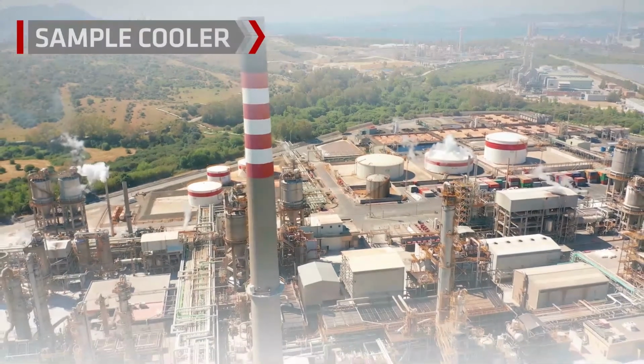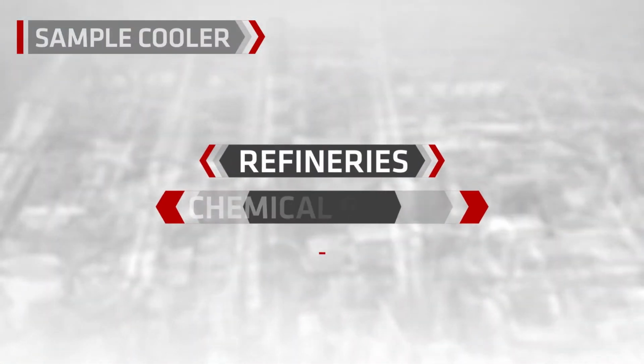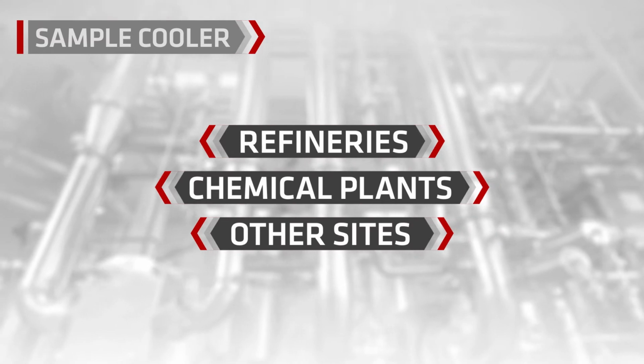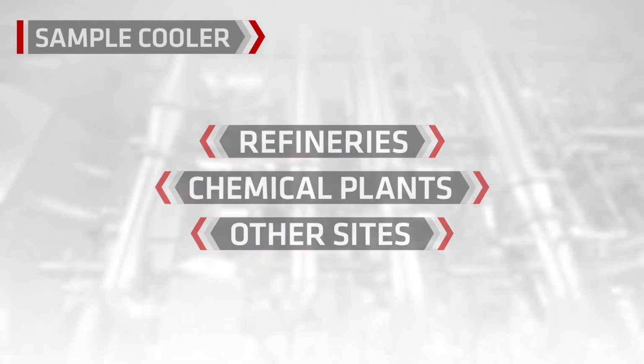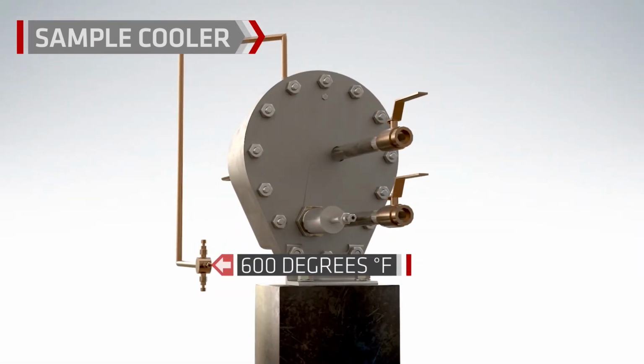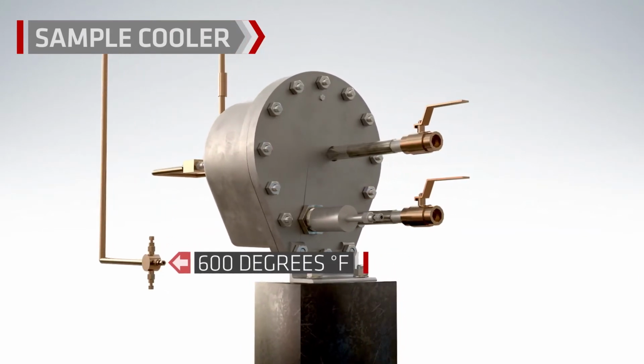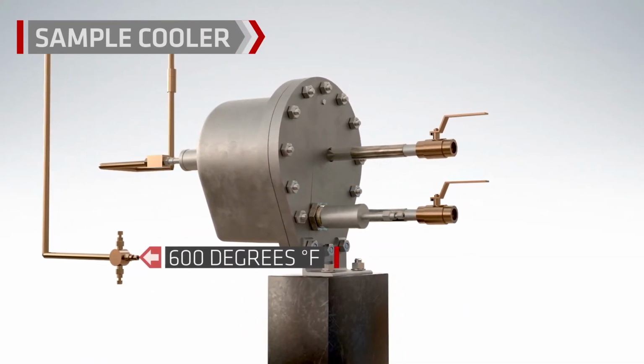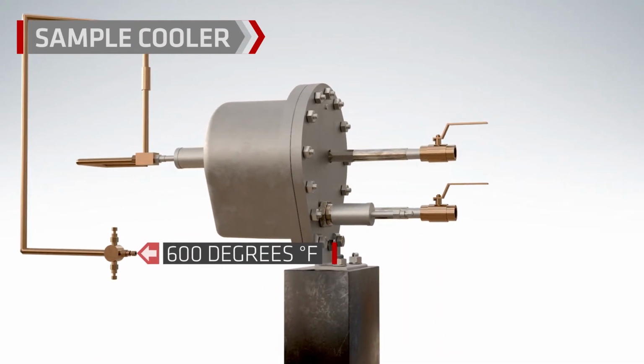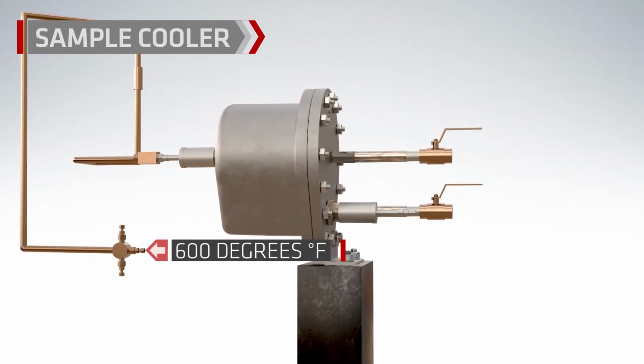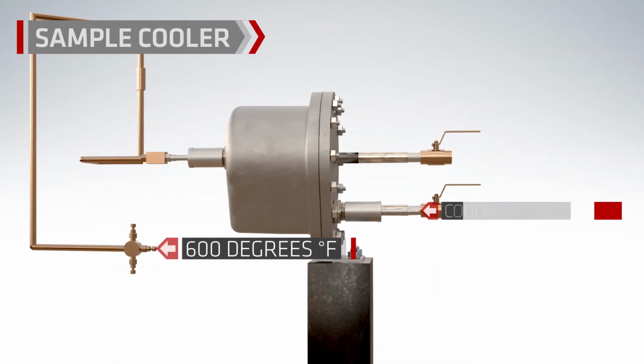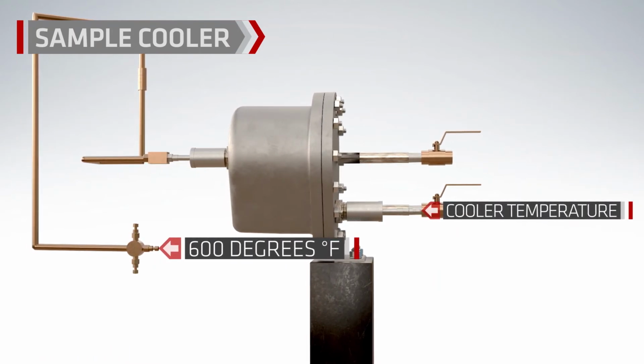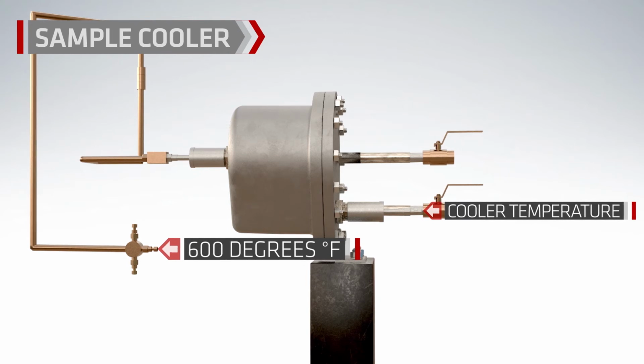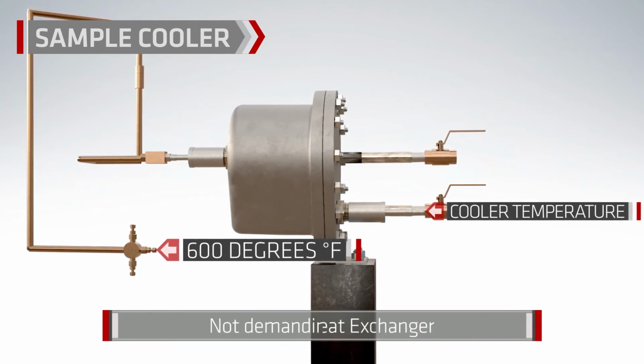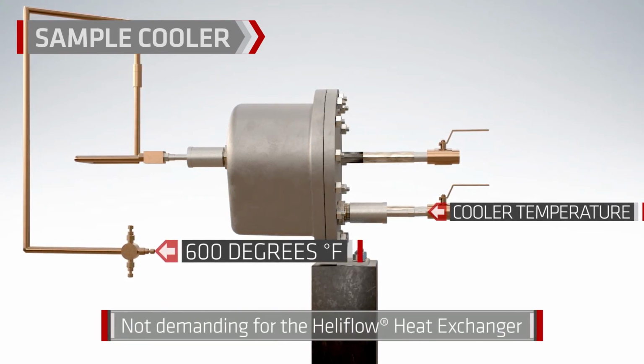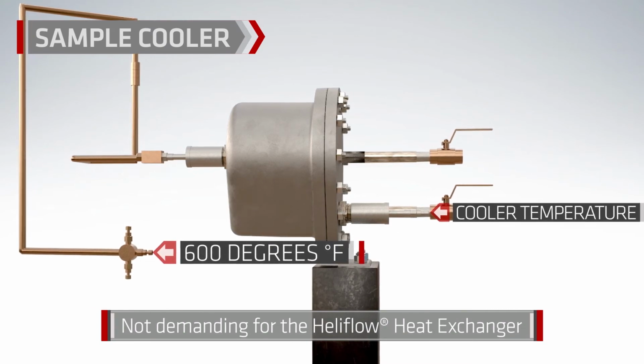A sample cooler is used in refineries, chemical plants and other sites where a process sample is needed. Often the fluid to be sampled is operating at 600 degrees Fahrenheit or more and cannot be safely handled or tested at that temperature. The sample cooler operates in an intermittent service with a hot sample fluid passing through the coil as needed, and a cooling medium is constantly flowing on the shell side. Once the sample fluid hits the bundle, it cools to a temperature that can be handled. This type of application is thermally demanding for a traditional shell and tube heat exchanger, but not for the Heliflow heat exchanger.